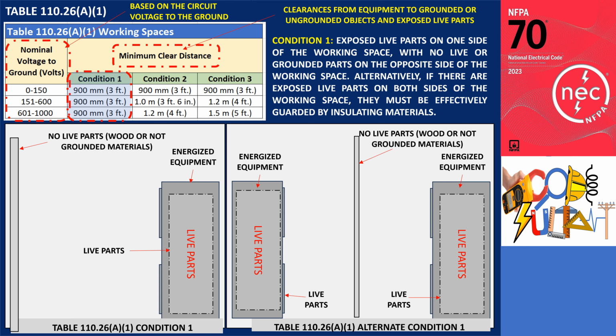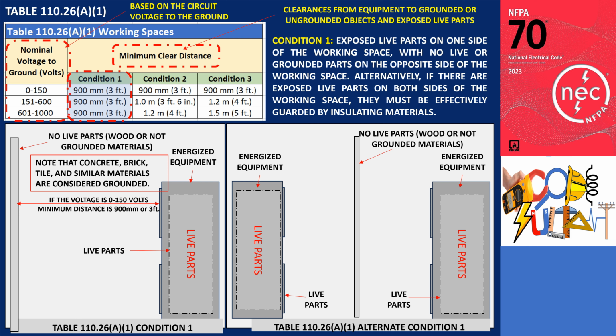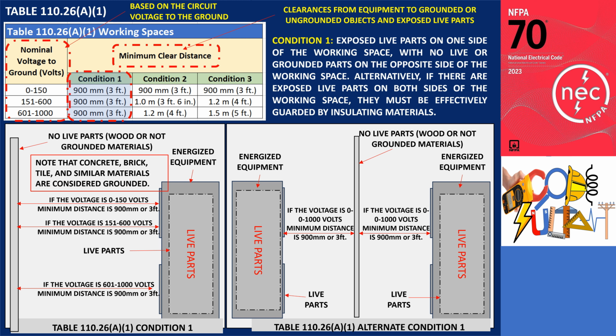It is crucial to note that surfaces like concrete, brick, tile, and similar materials are considered grounded. Therefore, if the voltage of the energized equipment falls within the range of 0 to 150 volts, the minimum clearance distance from the wall should be 900 mm or 3 feet. In the case of voltages ranging from 151 to 600 volts and 601 to 1000 volts, the required depth of the working space remains the same, with a minimum of 900 mm or 3 feet.